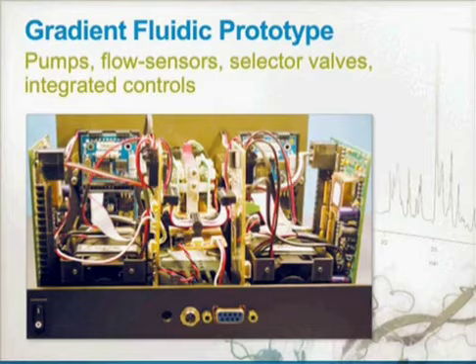Anything other than that, what we found was that the lifetime of the digestion column really suffered. Every time we took a hit from a mixing standpoint or from a stability standpoint, it essentially reduced the amount of active trypsin in the flow path. So what we found in the end is when we had it optimized, we could run this system without stop for dozens and dozens of runs with no obvious drop in performance. So we got it right. And the essence of that was achieving this really micro-scale or nanoscale titration event that we needed.